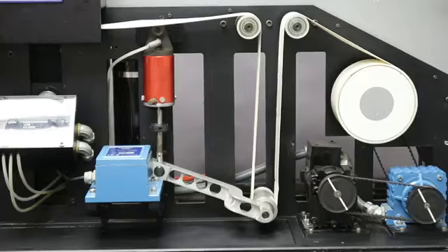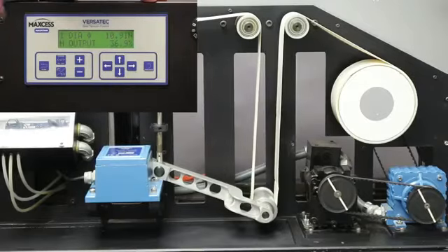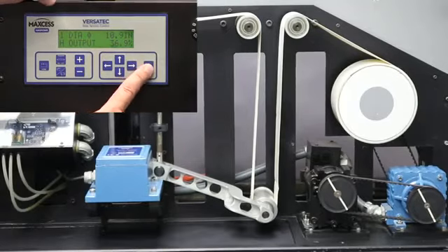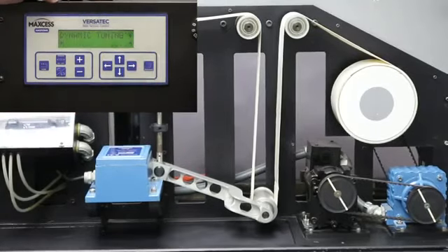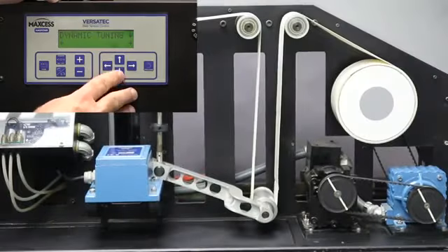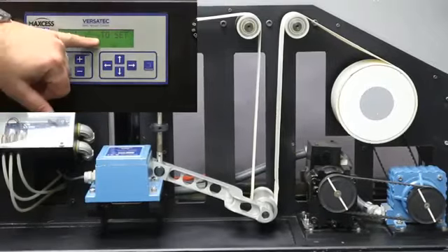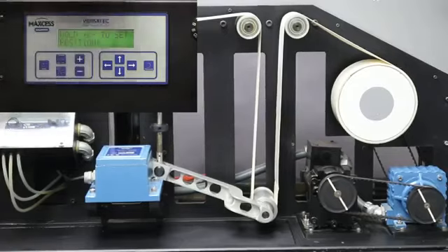So in this particular control, and what I'm going to show you is common for a lot of our different controls in the tuning method and the setup, but we're going to show you on the Versatec. The first thing I'm going to do is hit Program. It's going to take me directly to something called Dynamic Tuning. With the machine not running, I'm going to hit the down arrow, and it's telling me to hold the plus and minus key to set the position.